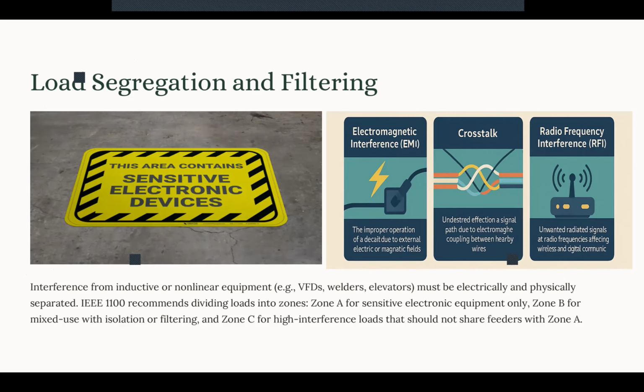Now, when it comes to loads, segregation is very important. We said zone A is exclusively for SEEs, sensitive equipment. Zone B is mixed, but it should have filtering. And zone C is high interference, so the problem-making equipment. We need to isolate the sensitive equipment. This way we mitigate or reduce those problems. We don't have EMI. We control the EMI. We control the crosstalk. And we control the radio frequency interferences when we talk about the system. And don't let the zones affect each other.